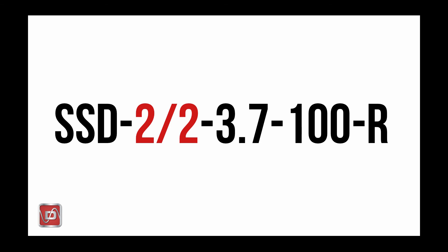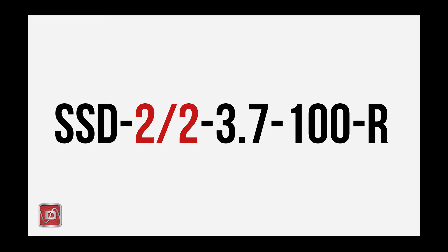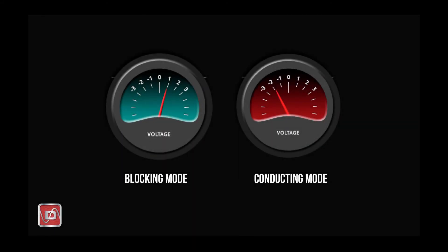So, a minus 2 volt to plus 2 volt product blocks DC current flow until the voltage between the terminals tries to exceed either minus 2 volts or plus 2 volts. You will notice that these numbers are equal, so the device has a symmetrical characteristic. For a minus 3 volt to plus 1 volt product, note that this is asymmetrical and it blocks a greater negative voltage than a positive voltage. So, why is that needed? Well, this device is typically connected to a cathodically protected structure that is shifted to a more negative voltage compared to ground or some other structure. So, the device threshold can be arranged to address this shift. In reality, most structures with CP can accept either the minus 2 plus 2 or the minus 3 plus 1 device.